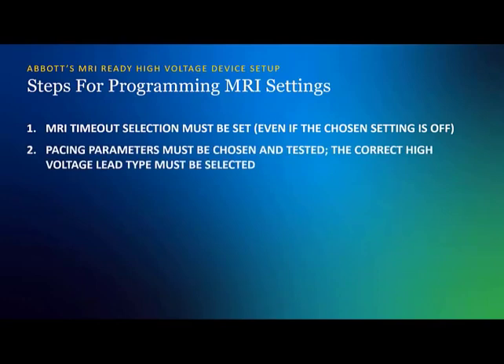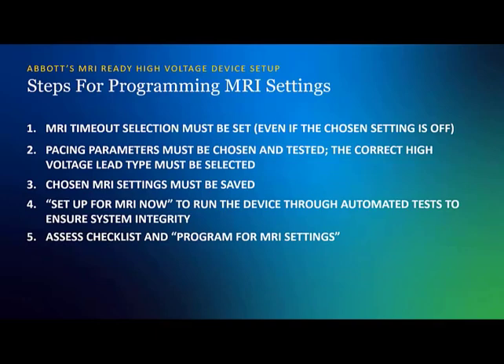It is important to note that it is necessary to proceed through every step in this process in order for the device to accurately switch into MRI settings. An MRI timeout selection must be set, even if the chosen setting is off. Pacing parameters must be chosen and tested. The correct high voltage lead type must be selected, and the MRI settings must be saved. This then activates the Setup for MRI Now button, which will run the device through automated tests to ensure system integrity. After assessing all factors of the MRI checklist and reviewing chosen MRI parameters, Program MRI Settings can then be pressed.